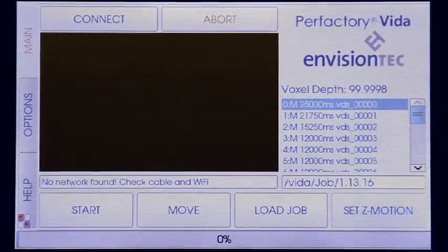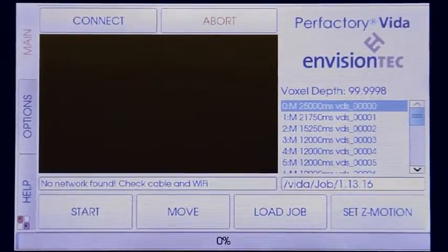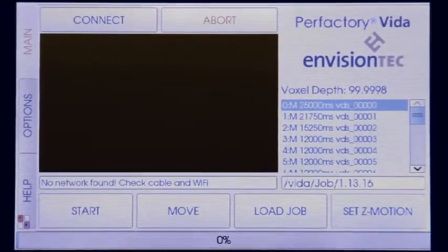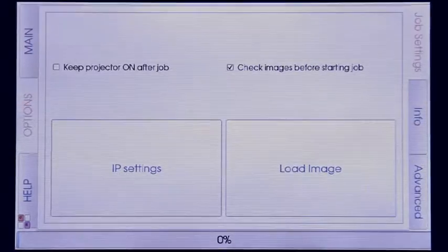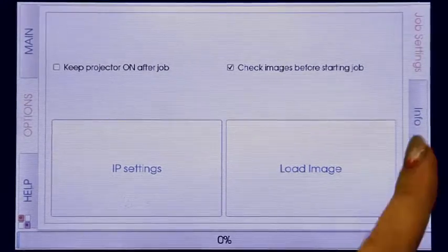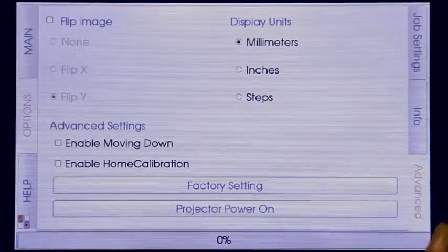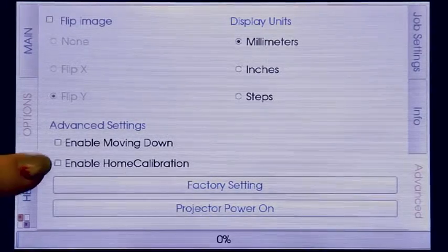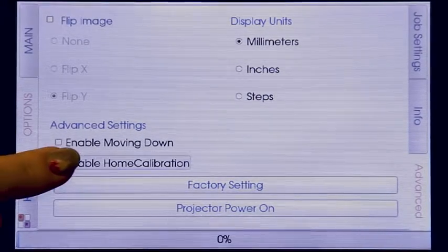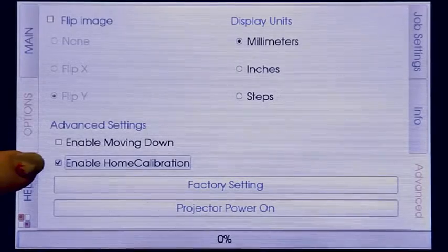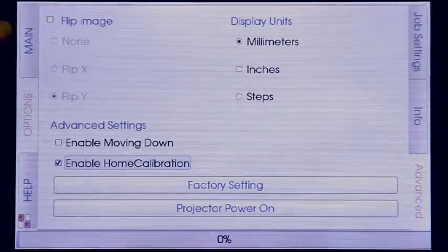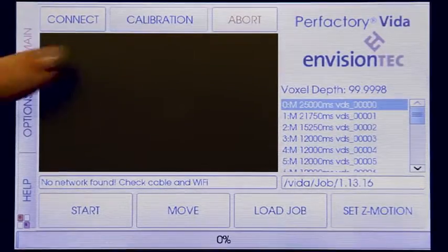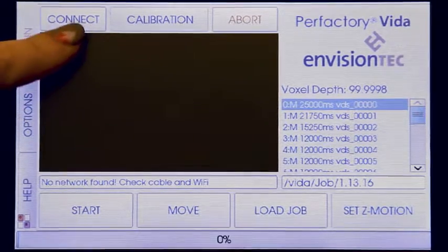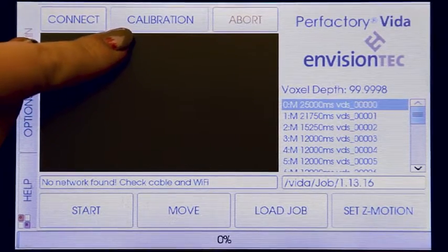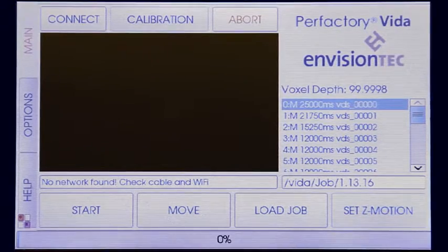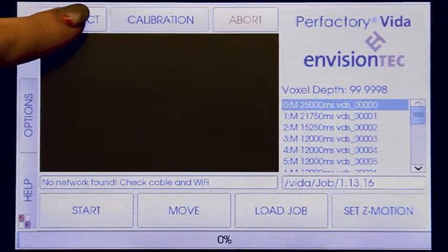basement. To begin, we're going to go to our screen, make sure our Vida is turned on. We're going to go into the Options tab, go into the Advanced tab, and select Enable Home Calibration. Once the check is in the box, we're going to go back to the Main tab. And at the top, you'll see a new button next to Connect that says Calibration. First thing I'm going to do is connect the motion controller.